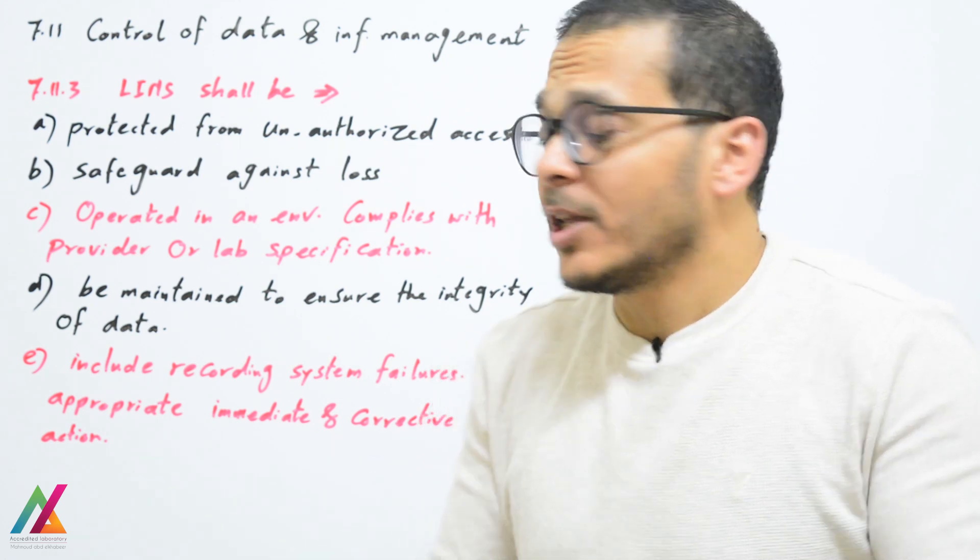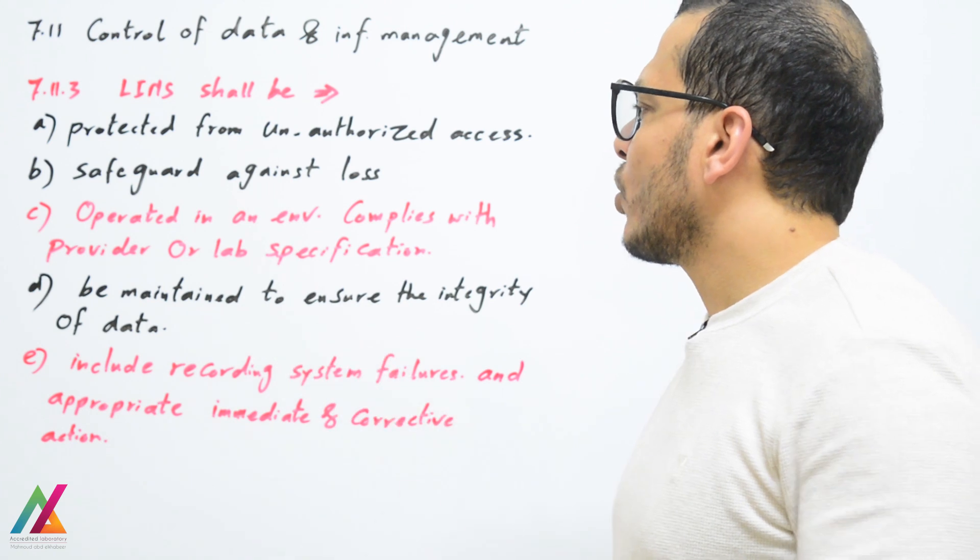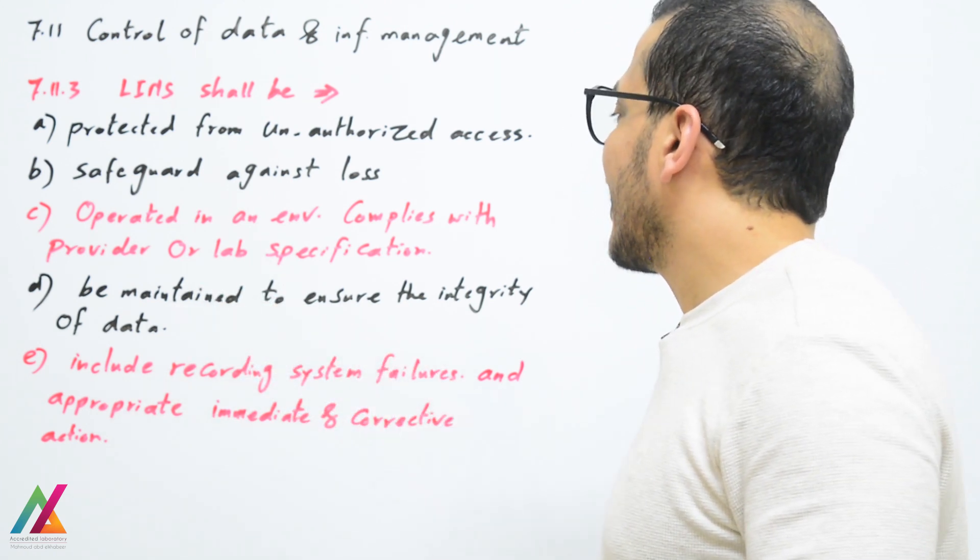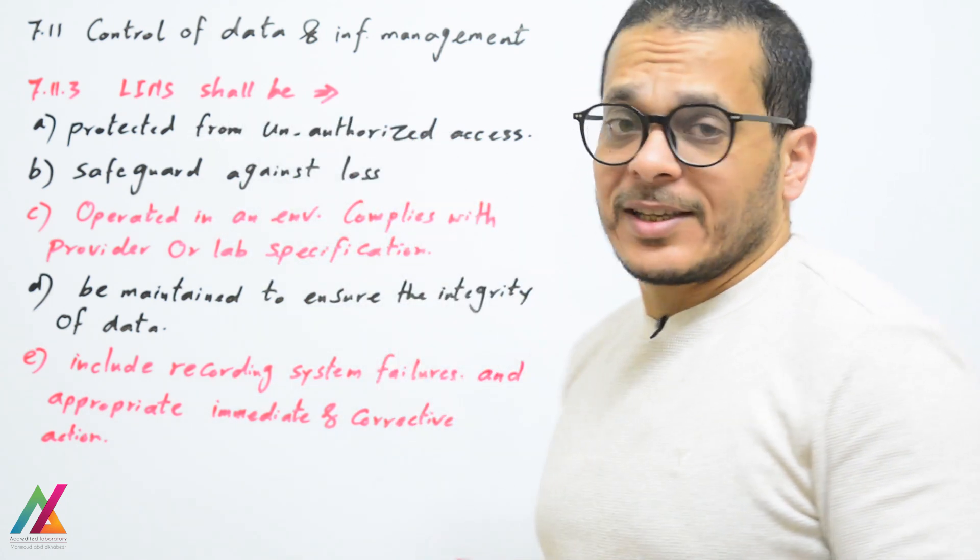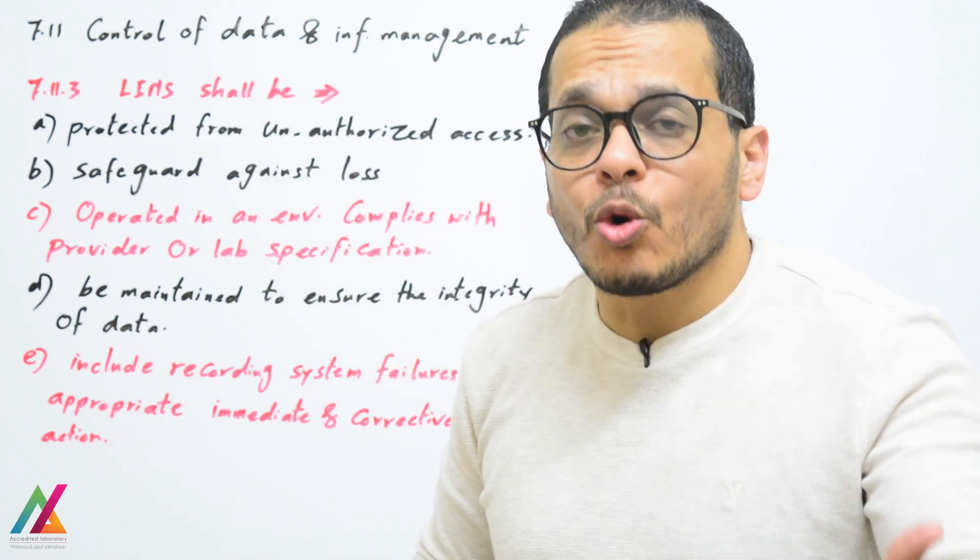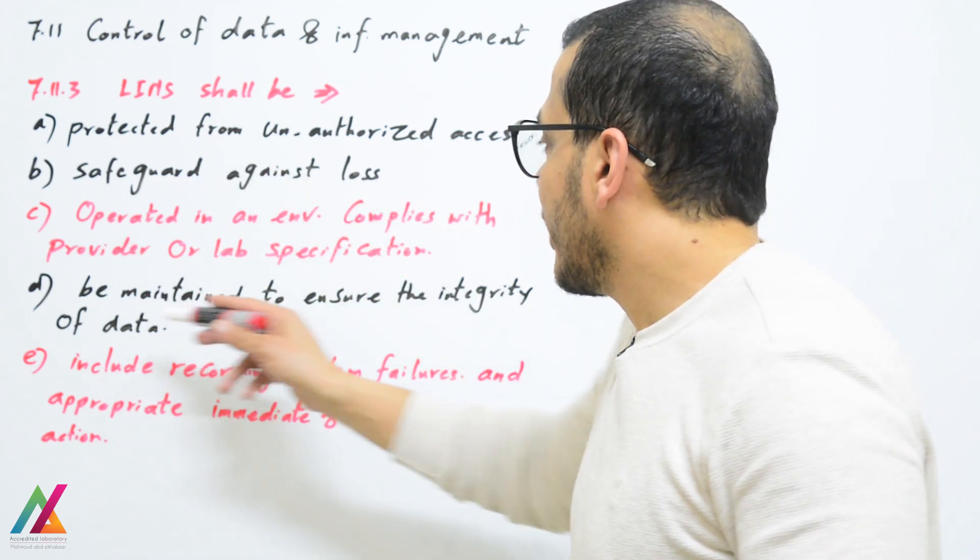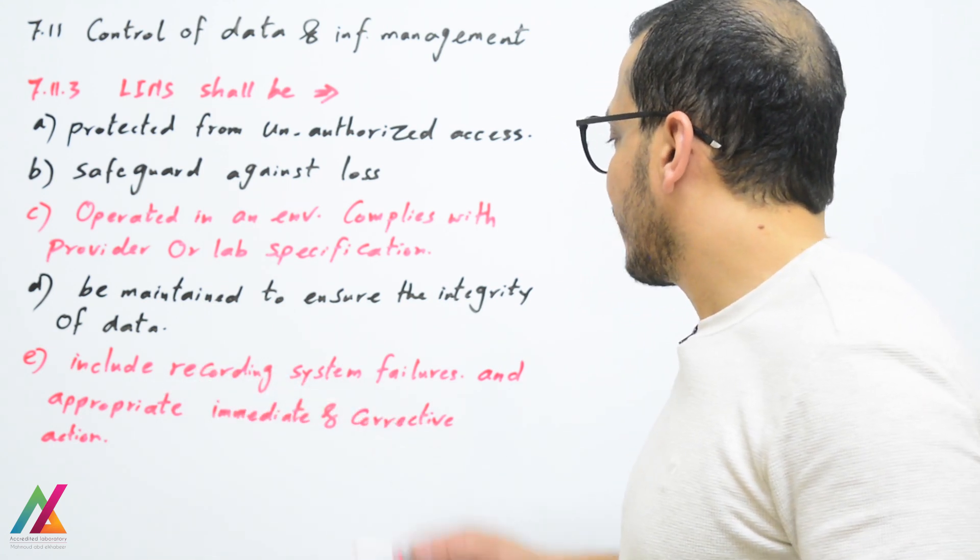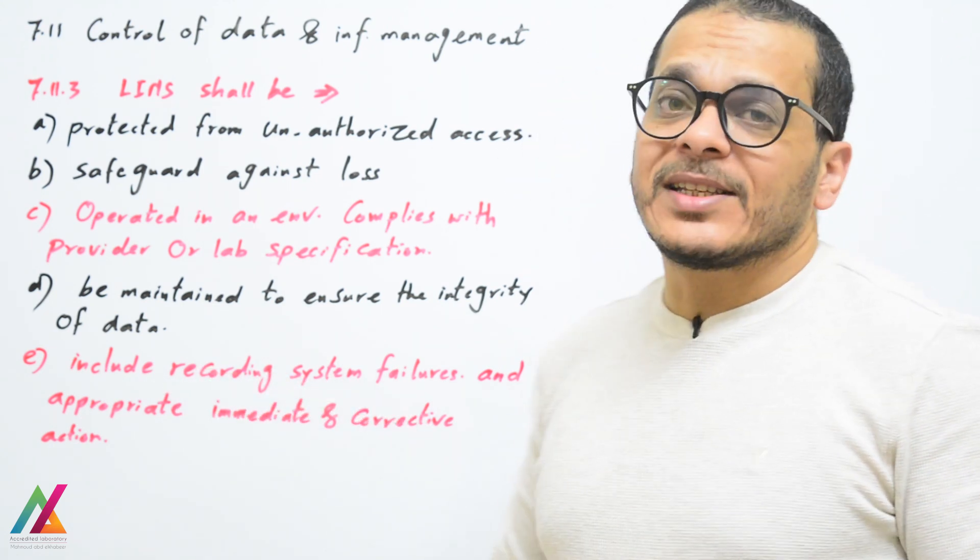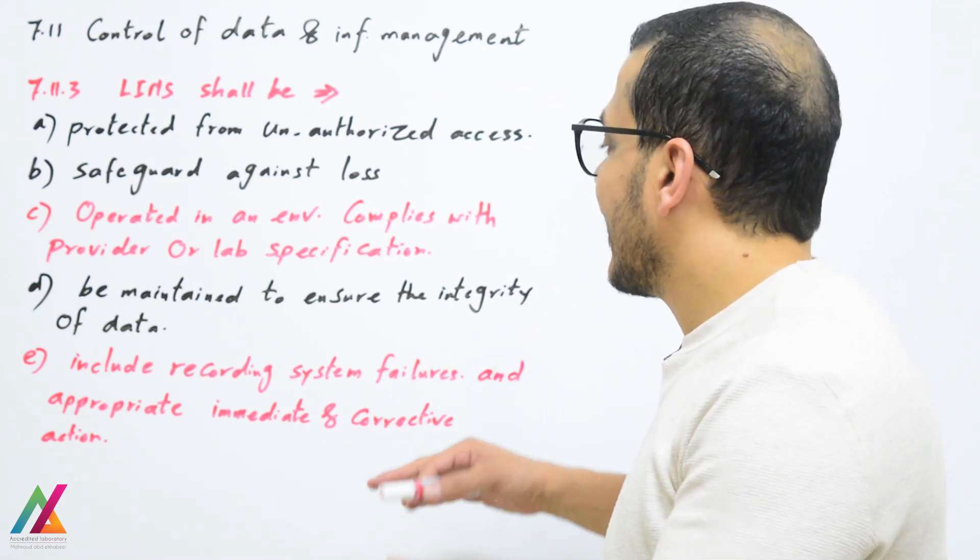LIMS should be operated in an environment that complies with the provider or lab specification and be maintained to ensure the integrity of data. If you protect access to data and safeguard against loss, that will ensure the integrity of data. Include recording system failures and appropriate immediate and corrective action. You should have appropriate corrective action in case of any failure inside LIMS.